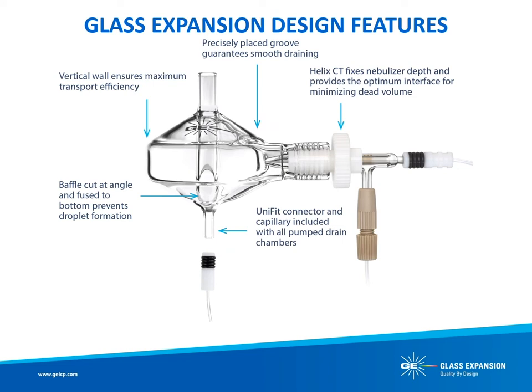Glass Expansion revolutionized spray chamber design for the ICP-OES and ICP-MS analyst by introducing cyclonic spray chambers. Prior to the Glass Expansion Tracey cyclonic spray chamber, Scott-style spray chambers were the standard option provided with your ICP. The design of Glass Expansion cyclonic spray chambers helps the ICP analyst achieve sensitivity gains, reduce washout times, and reduce matrix effects not possible with other designs. An indented groove is built into the top of the spray chamber and serves as a barrier preventing solution from being swept into the torch. The position and depth of this groove are critical. Note that the walls of the spray chamber have a vertical region, which is important for proper aerosol generation and affects transport efficiency to the torch.